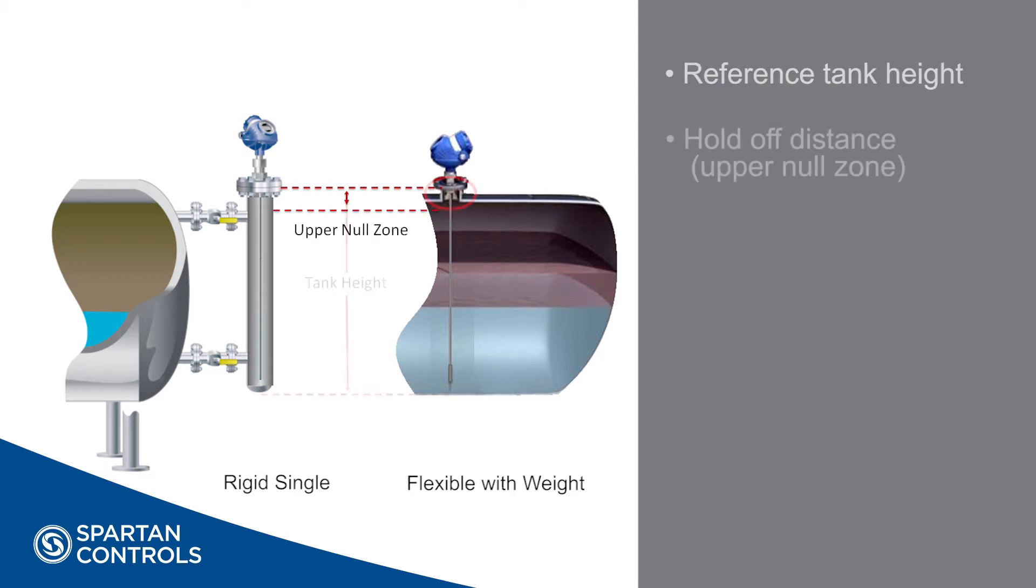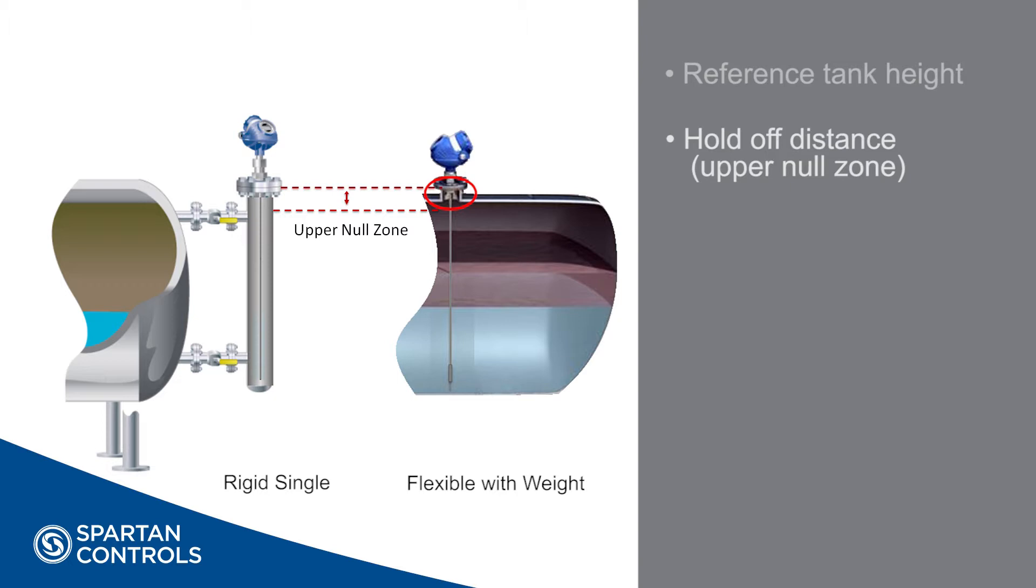Hold off distance or upper null zone is the area at the top of the tank the radar transmitter's configured to ignore. As a rule of thumb, guided wave radars cannot make a reliable measurement in the first six inches away from the flange. For this reason it is advisable that a null zone of at least six inches be configured. In nozzle installations, it is suggested that the null zone be configured for at least the nozzle's length to ignore any noise that may appear in the nozzle. On bridle installations, the null zone should be at least the distance from the transmitter flange to the top process tap.